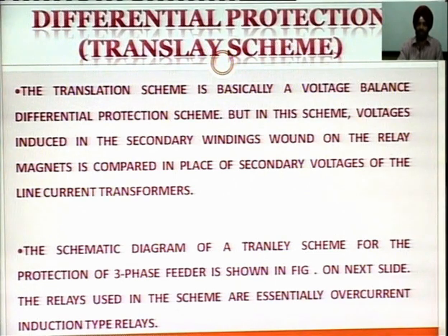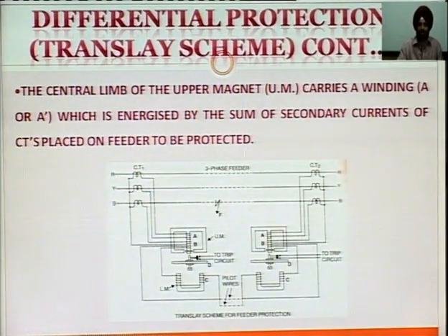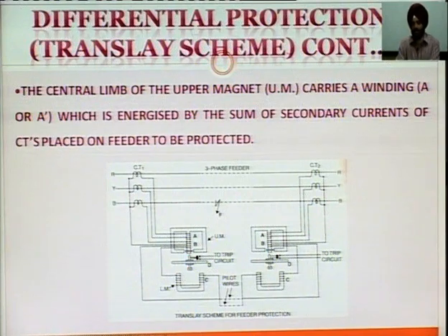The relay used in the scheme is essentially an overcurrent induction type relay. The center limb of the upper magnet carries the winding, which is energized by the sum of the secondary currents of the CTs applied on the feeders to be protected.